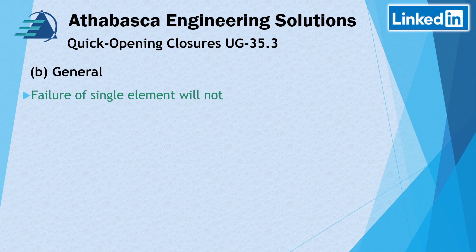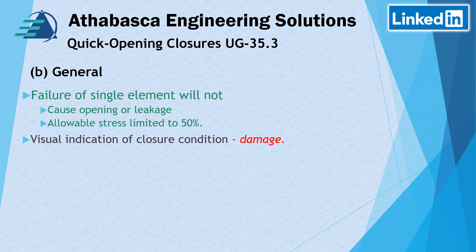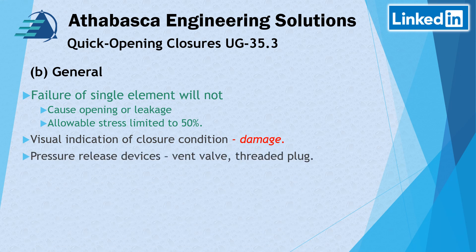For UG35.3, holding elements are parts of the closure used to hold the vessel closure and provide the force required to seal the vessel — they can be hinge pins or bolted flange pins. The general requirements are similar to UG35.2. Failure of a single element will not cause opening or leakage, and allowable stress must be limited to 50%.